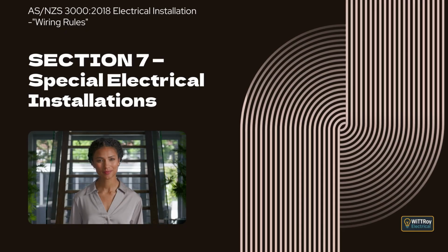Clause 7.3.5.2.1 General. This clause explains that prospective short-circuit current and prospective earth fault current must be assessed for each electricity generation system or combination of systems supplying an installation. It explains that the short-circuit rating of protective devices must not be exceeded under any intended operating condition. It also explains that where electronic overcurrent protection is fitted within a generation system, such as in inverters, the system may automatically limit output current and may prevent the operation of external protective devices during fault conditions.